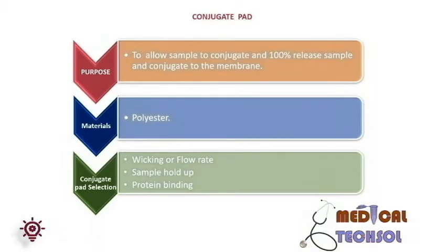The conjugate pad's function is to allow the sample to interact with the conjugate and achieve 100% release of the sample and conjugate to the membrane. General materials used are polyester (PET) or polystyrene pad. Factors to consider when selecting the conjugate pad are: number one, flow rate; number two, sample holding volume; number three, binding. The conjugate can be added into the pad via dipping or dispensing method.